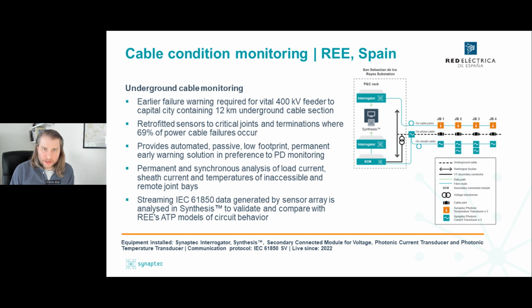So we've installed what I think is a very interesting system, which is monitoring the health of a very important 400 kV cable, which happens to be under Madrid Airport in Spain. And cables such as this span many miles. In this case, it's in a tunnel, but it could be in a duct or some other approach. And these are very difficult, time-consuming, and I guess quite unpleasant to have to inspect manually because of the distance involved.